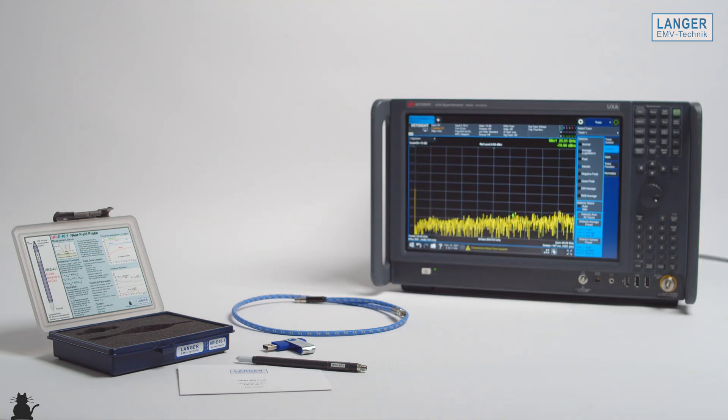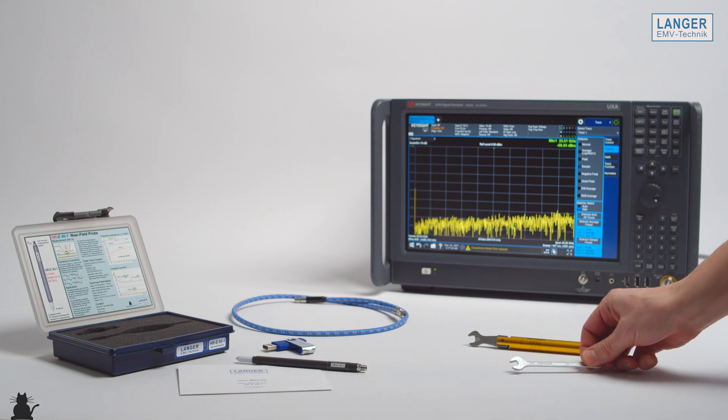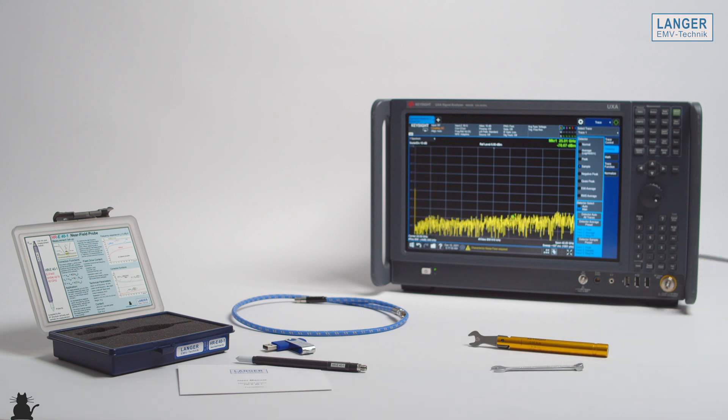For measurements with the HRE40-1 set, a microwave cable with 2.92 mm connector and an appropriate measuring device are required. In addition, a 5/16 inch torque wrench with 0.9 Nm and a ¼ inch open-end wrench are recommended for installation.